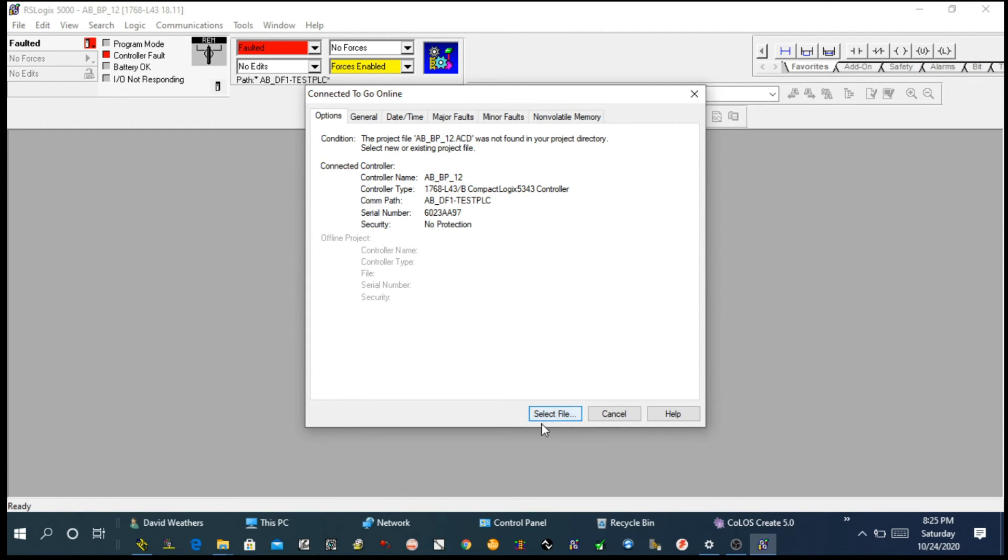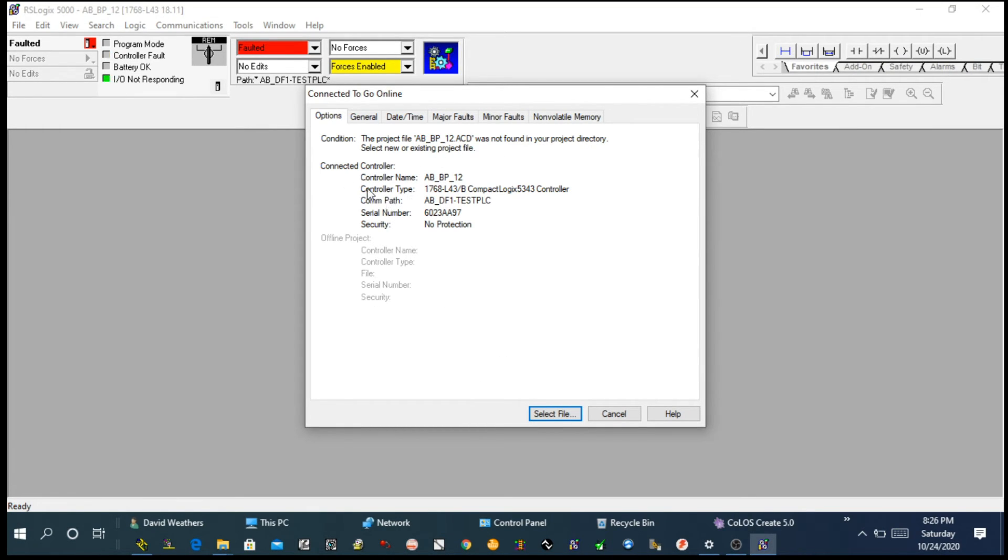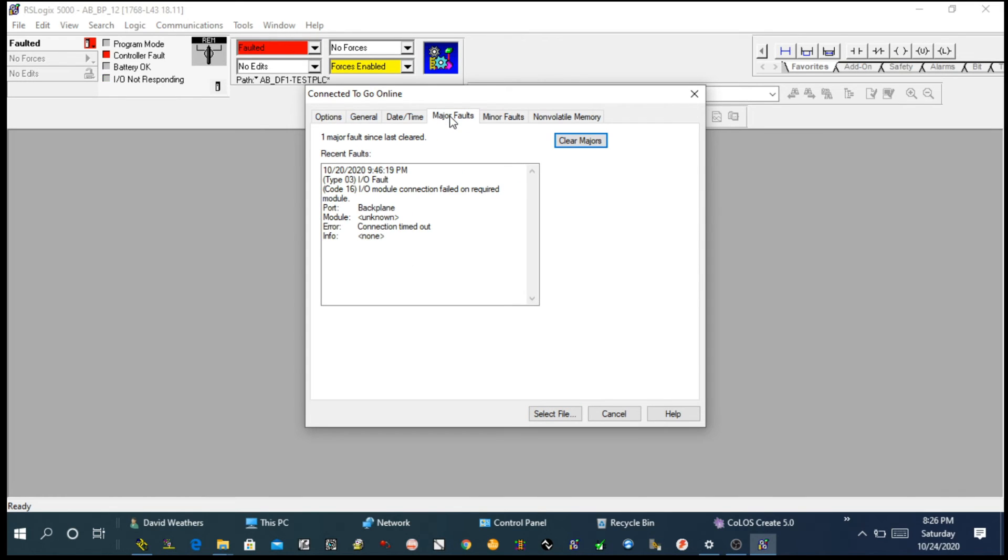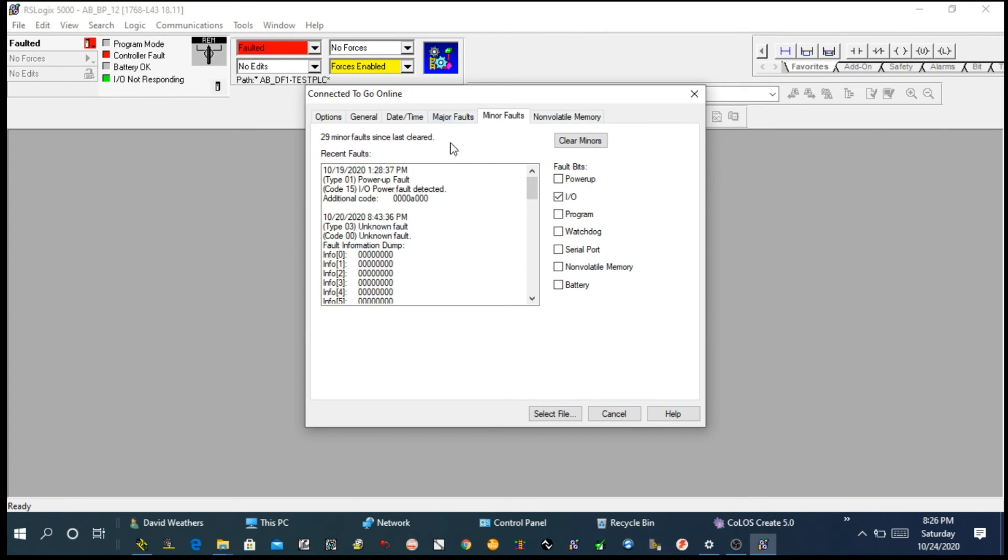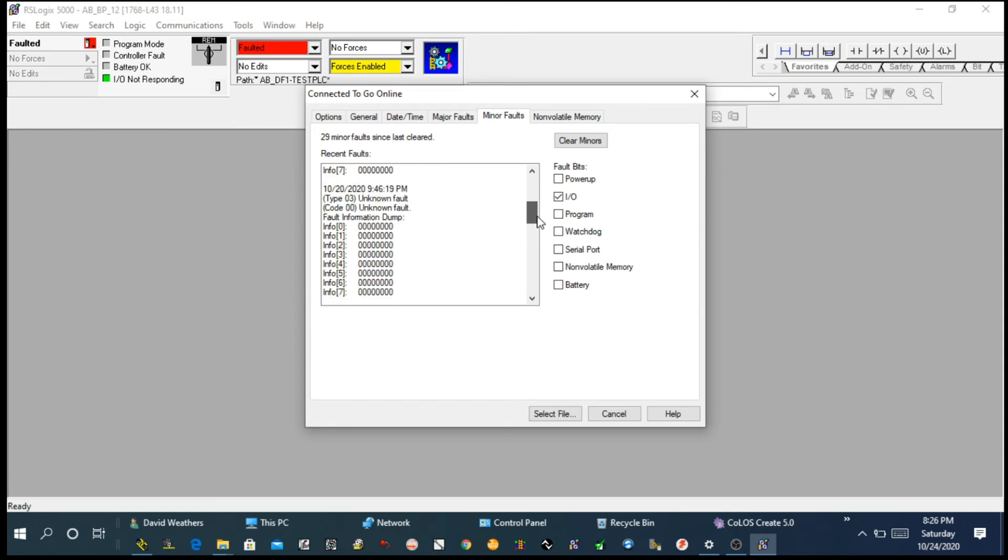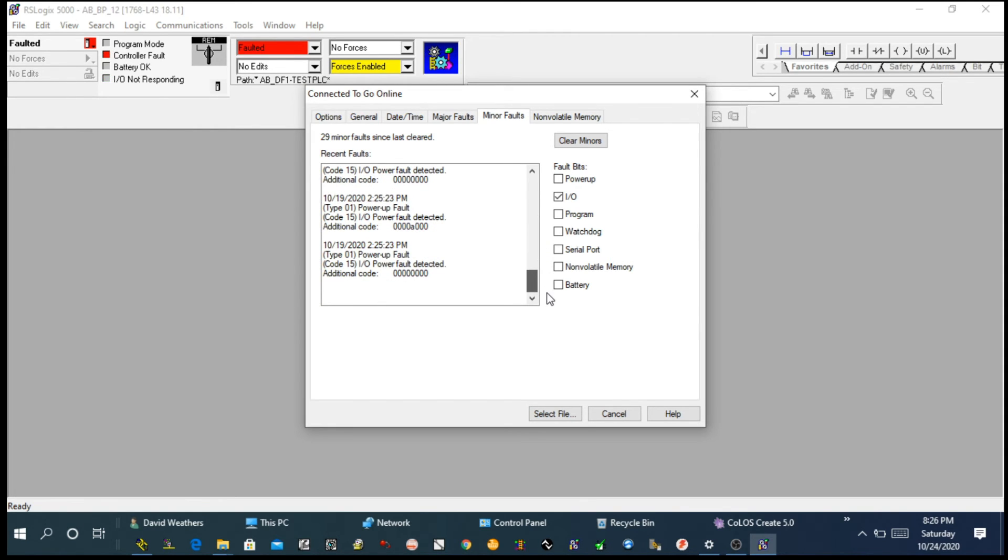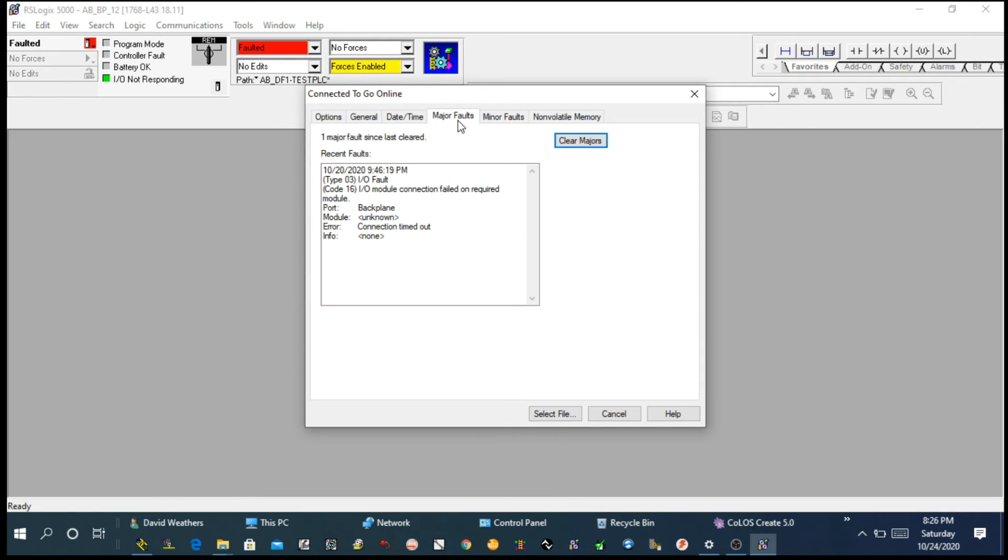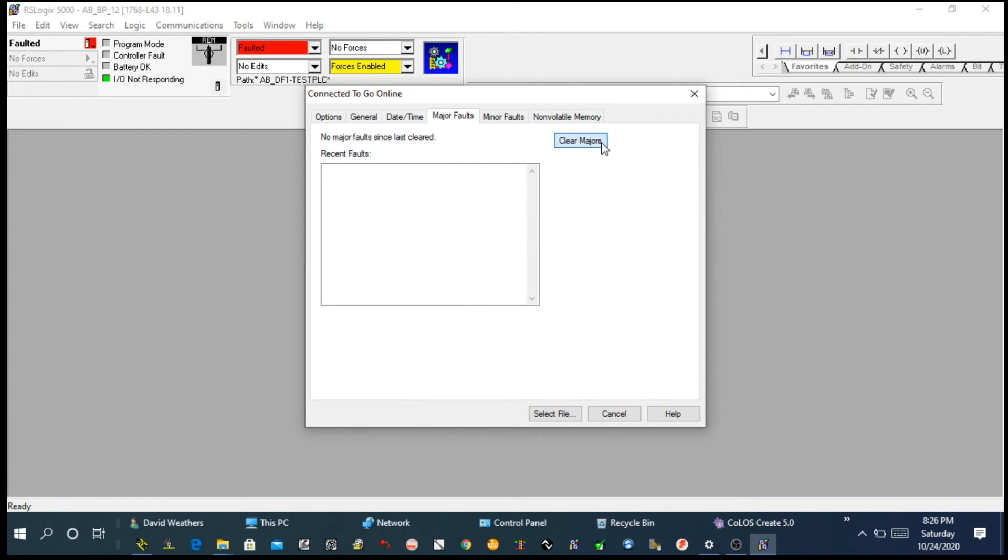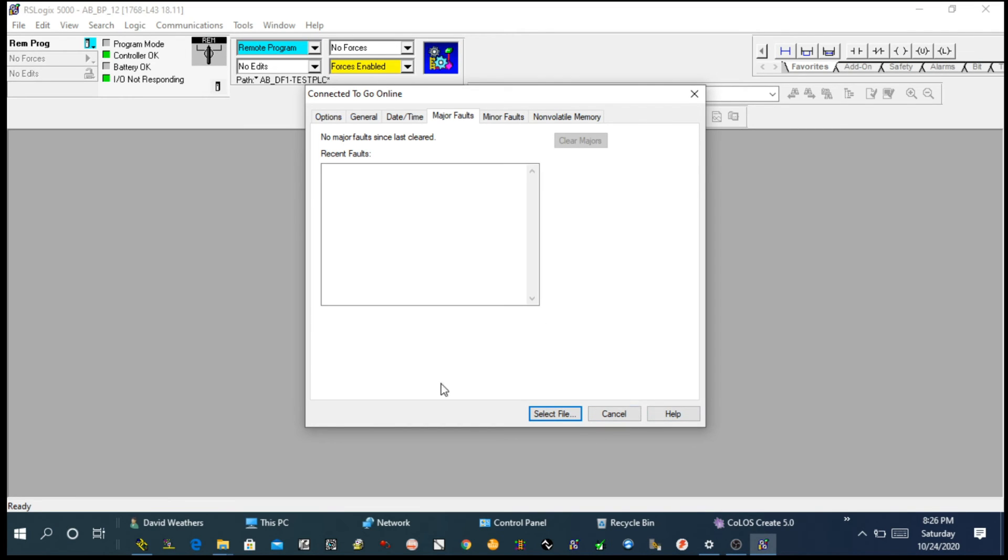As you can see, it appears a lot of red on the top. That red on the top is telling you that you have multiple errors or faults on this PLC. In my case, I have a major fault. There will be all lists, whatever the program you're using, your PLC information. On the top there are a couple other options like General, there's Major Fault, then you have Minor Fault. Here's the list of faults. You can make a list, you can take a picture to be fixed in the future and come back. To clear fault, if you see here it says Clear Fault, you simply click on it. It will clear all the faults. You can see now on the top all are blue because they are just connected right now. They are on program mode. They are not at run mode. Program mode you always see a blue color.